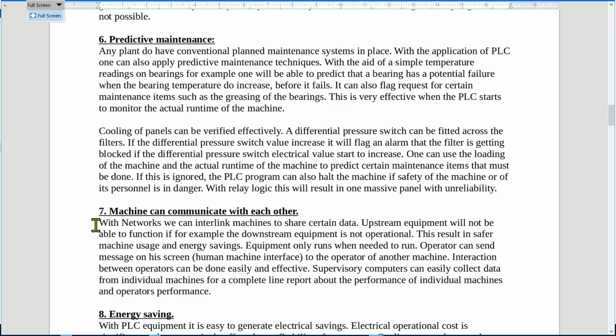Now, upstream equipment will not be able to function if, for example, the downstream equipment is not operational. This is more for cascading, where you have, for example, a conveyor must be started only when the upstream conveyor is started, or else you will create havoc. So the machine can start in sequence and in proper sequence. Now this results in a safer machine usage and energy savings. The equipment only runs when needed to run.